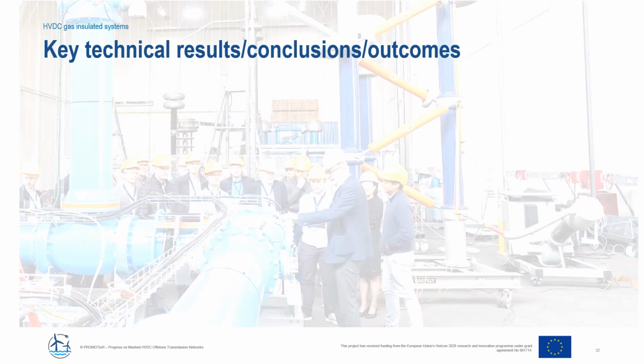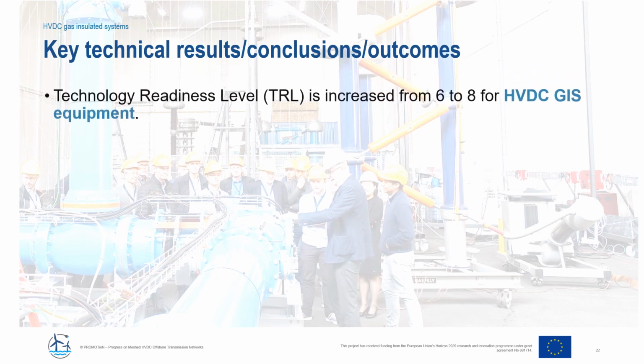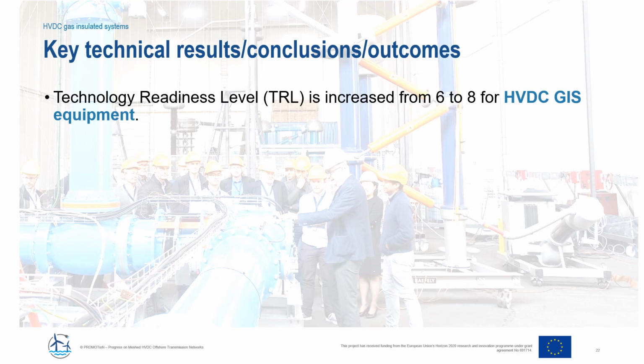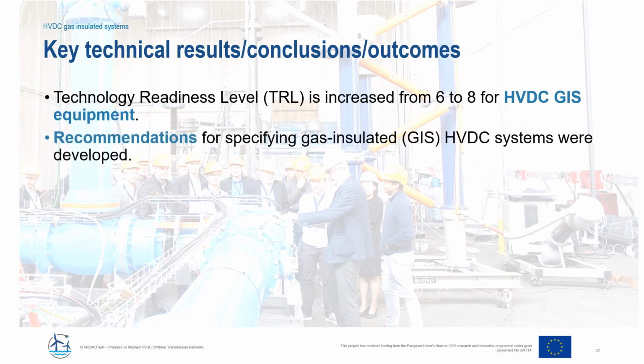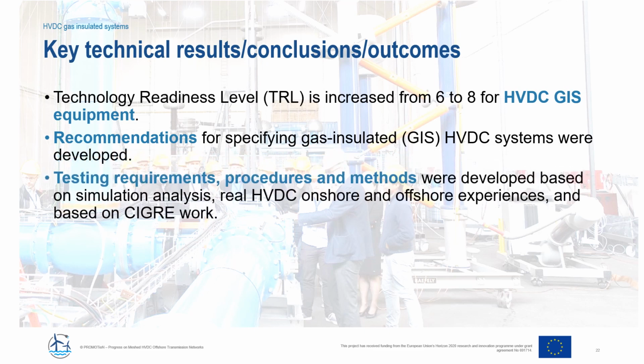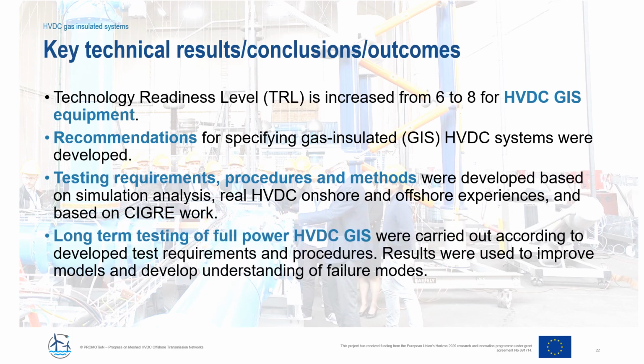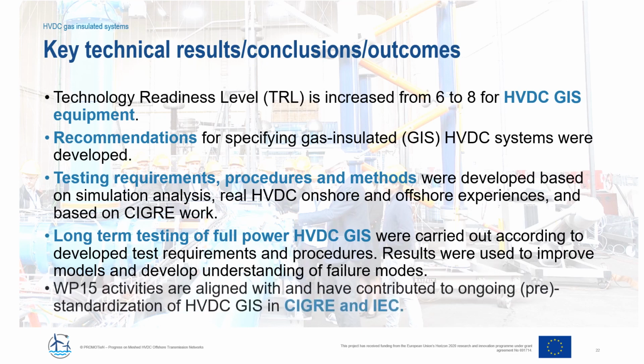Let me now summarize the key technical conclusions from Work Package 15. The technology readiness level is increased from 6 to 8 for an HVDC gas-insulated system. Recommendations for specifying gas-insulated HVDC GIS were developed. Testing requirements, procedures, and methods were developed based on simulation analysis, on real HVDC onshore and offshore experiences, and based on the CIGRE work. Long-term testing of full-power HVDC GIS was carried out according to the developed test requirements and procedures. The results were used to improve the models and develop understanding of failure modes.